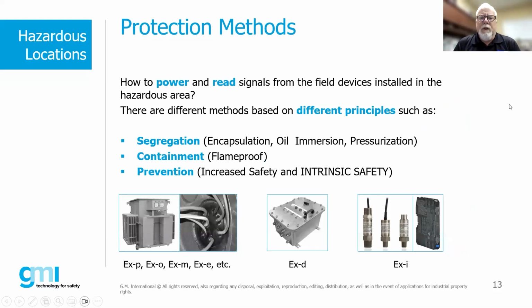Next. There's a bunch of different protection concepts, but we pretty much segregate these into three different methods. There's segregation, where we're keeping a flammable gas vapor mixture away from potential arcing or sparking. We can do this by encapsulating equipment, using oil immersion, or pressurized panels, keeping a flammable gas outside of either a room or a cabinet.